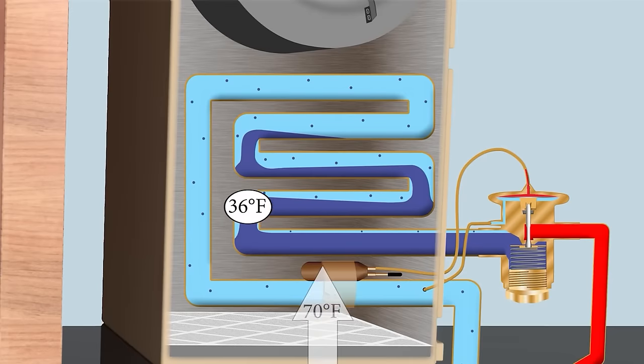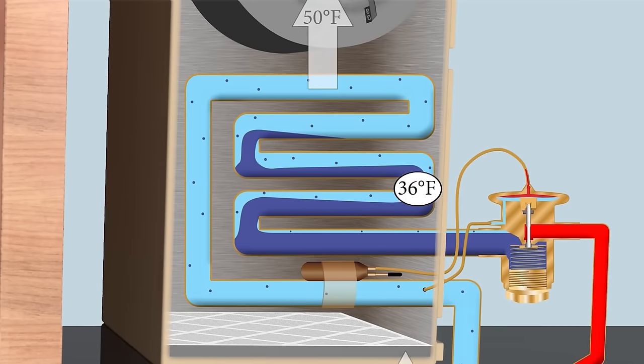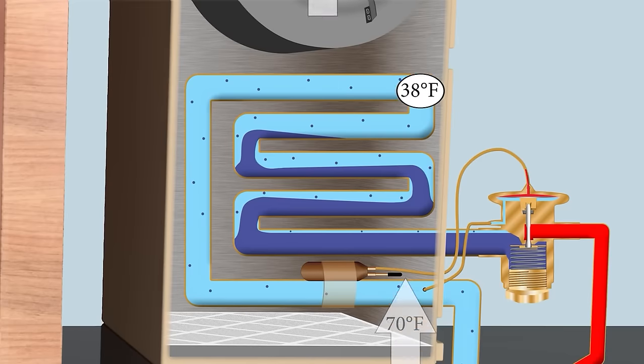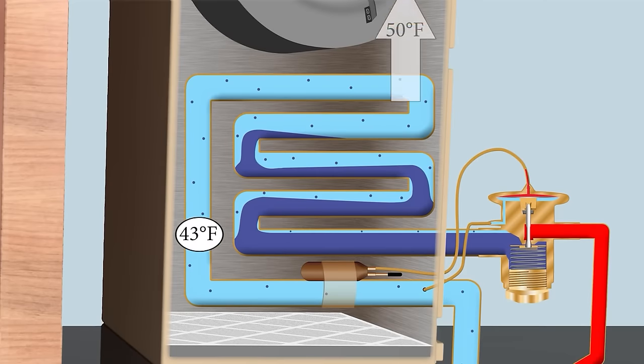If there's not enough air — or no air — traveling across the evaporator coil, the refrigerant is not going to have any heat to absorb. The job of the refrigerant is to absorb heat, which causes it to increase in pressure. If there's no heat, it's going to remain low in pressure — the pressure is going to lower and lower because you have low indoor airflow.